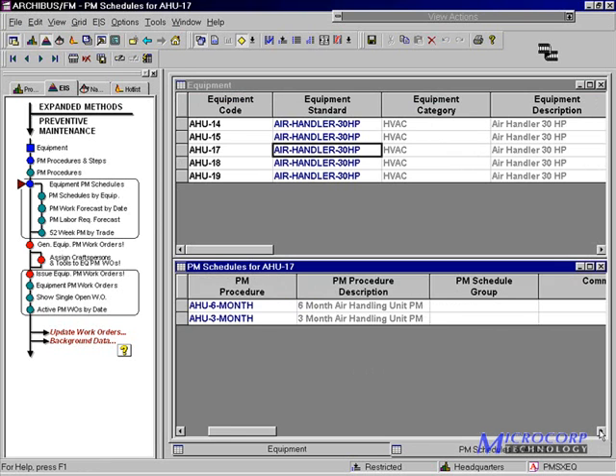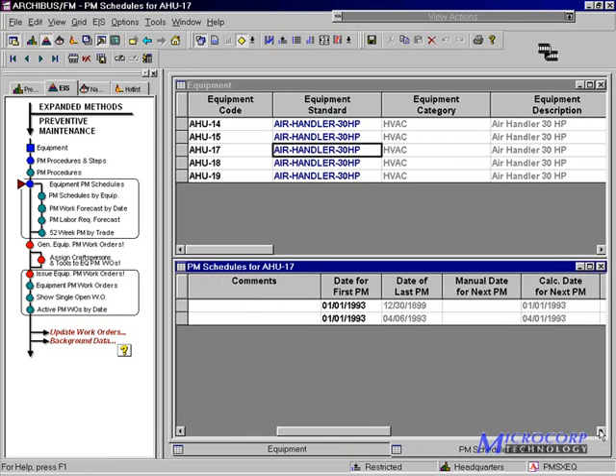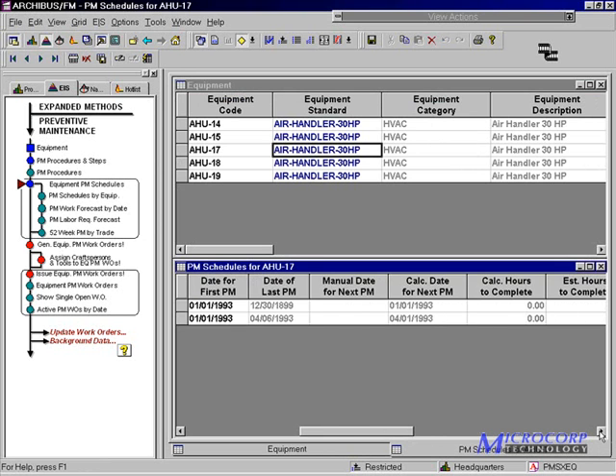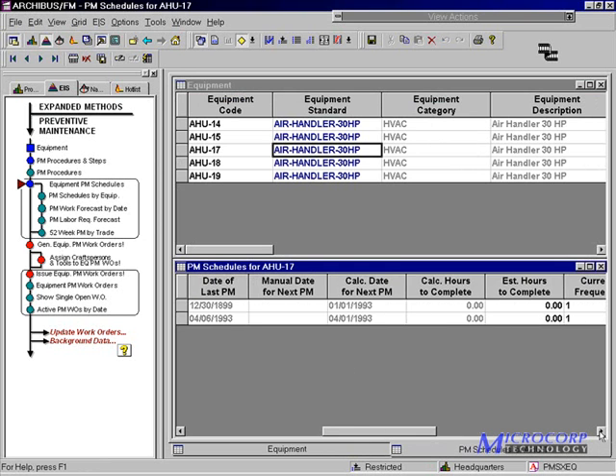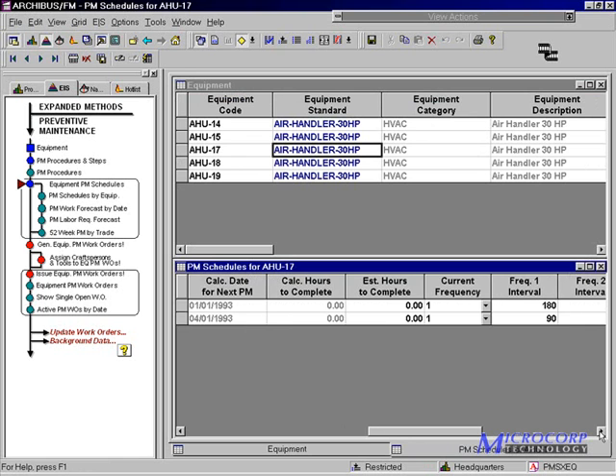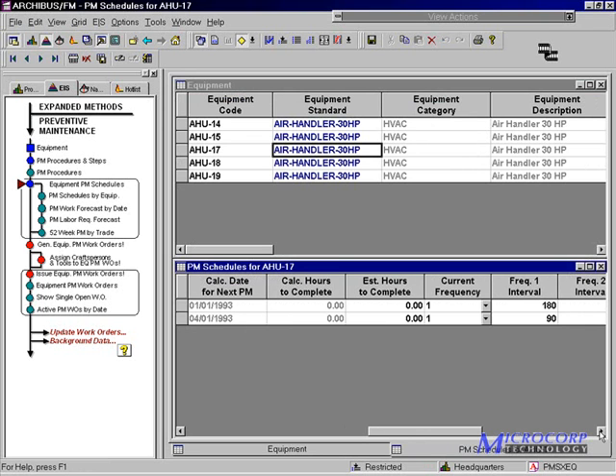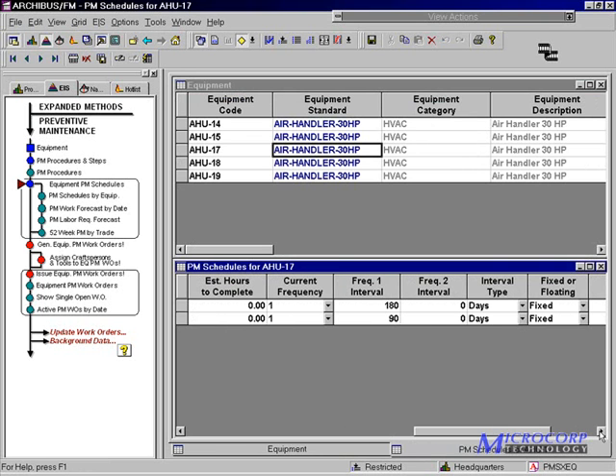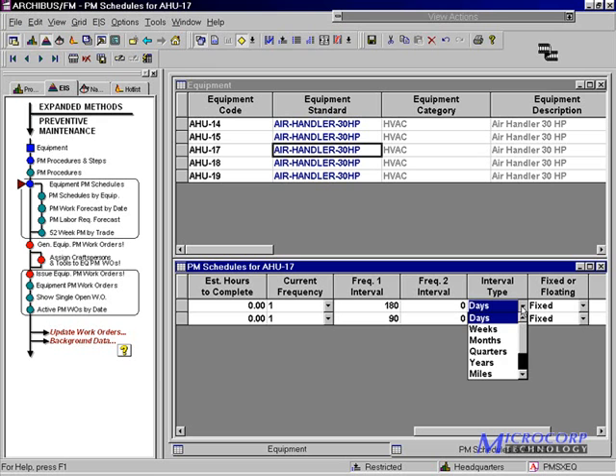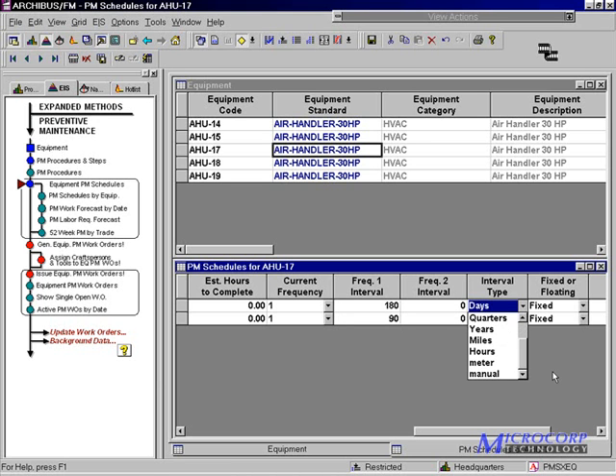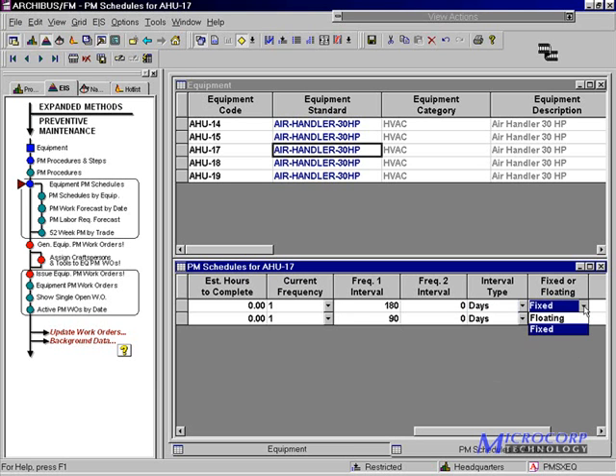The PM schedule includes information about the date of first PM, date of last PM, and date for next PM. It also includes the frequency with which it should be performed. The frequency is based on the type of interval and can be in weeks, months, years, or some form of meter reading.